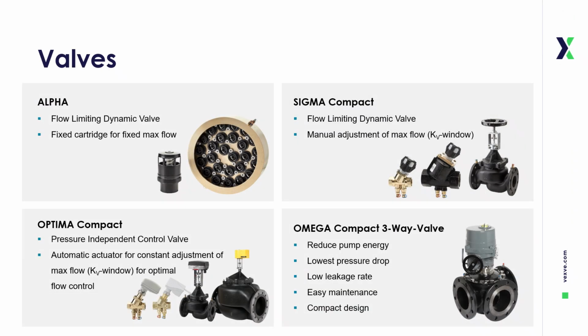Frese offers a complete portfolio of innovative valves, each designed to optimize flow control and energy efficiency across applications. All valves work by the same mechanical principles that eliminate pressure fluctuations across the valve opening. The Alpha Flow Limiting Dynamic Valve provides a fixed cartridge design for a predetermined maximum flow. Simple, reliable, and effective. The cartridge is positioned in line, and the flow setting cannot be tampered with.